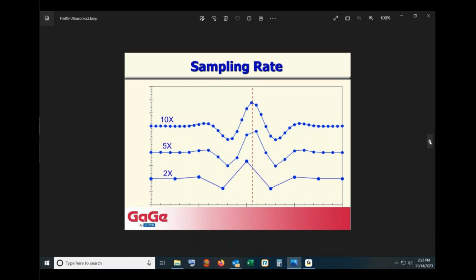So we've respected the Nyquist criteria by sampling at exactly twice, in fact, the central frequency of that ultrasonic echo. And you can see on the bottom image, we do get a rough idea of what the echo looks like, but it's a pretty crummy view of the signal. Once we move up to 5 or even 10 times sampling, now we're sampling at 10 times the central frequency of the ultrasonic echo, we can see that we get a really proper view of the echo. So really, we recommend, in the case of ultrasonics, that you sample at about 10 times the central frequency of the ultrasonic transducer.